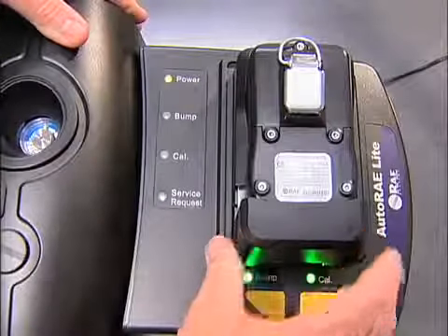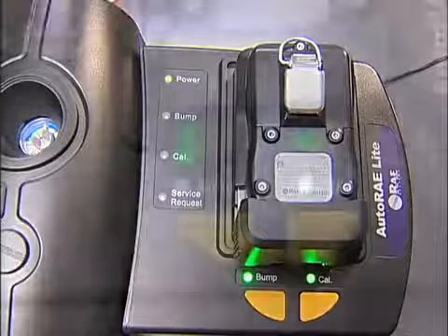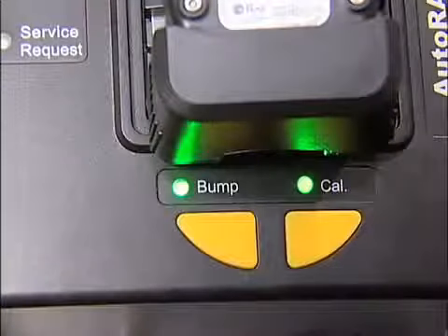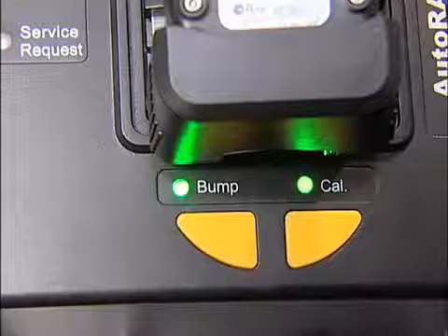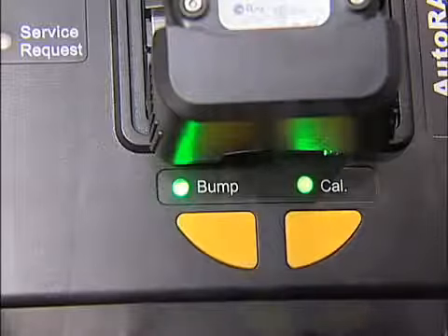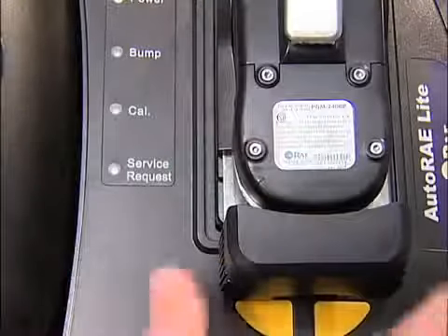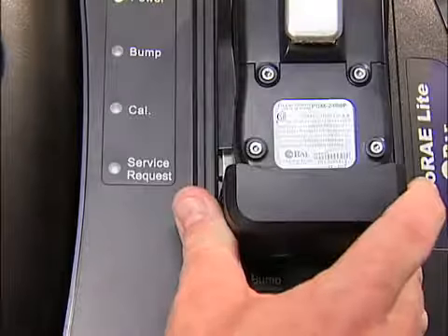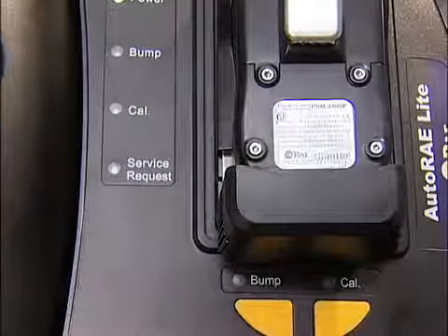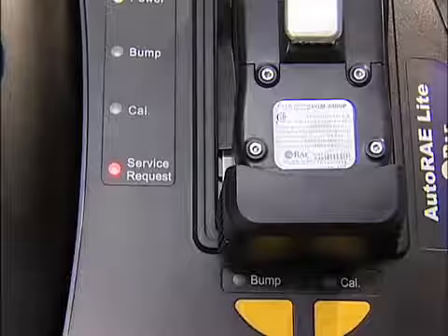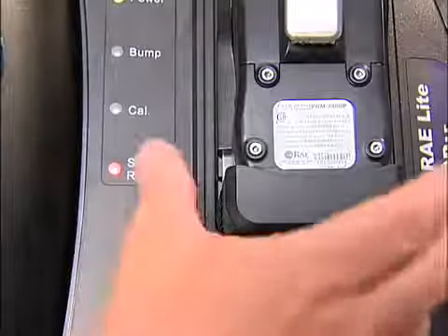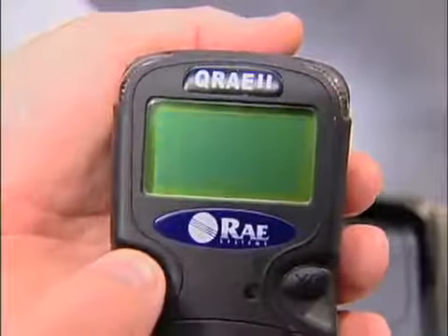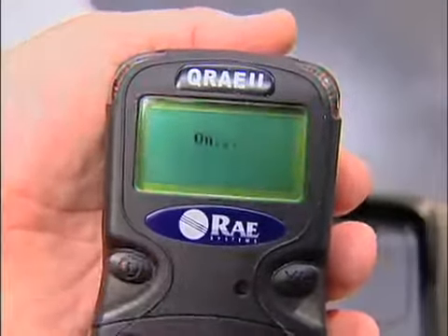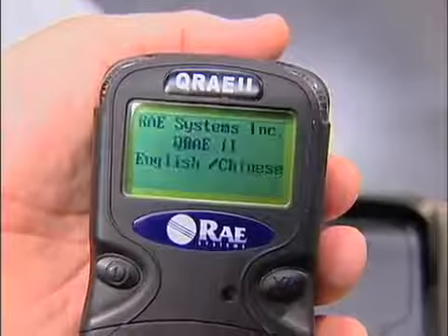Slide the locking mechanism up so that the QRAE II is held in place. The 2 LEDs above the buttons should glow green. If not, make sure the QRAE II is firmly seated. If the service request lamp glows after you slide the locking mechanism, it is likely alerting you that the QRAE II has not been turned on. Remove it, turn it on, and place it again in the dock.